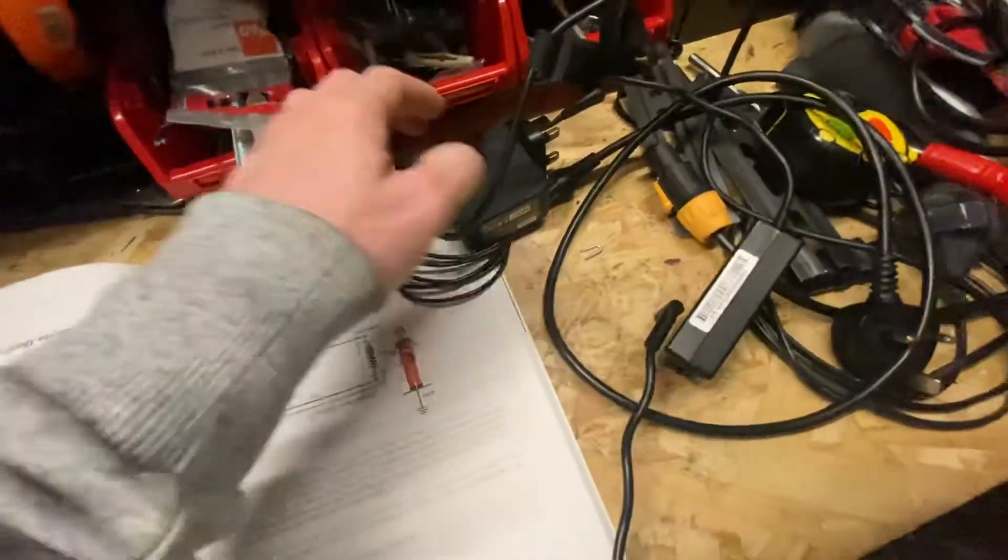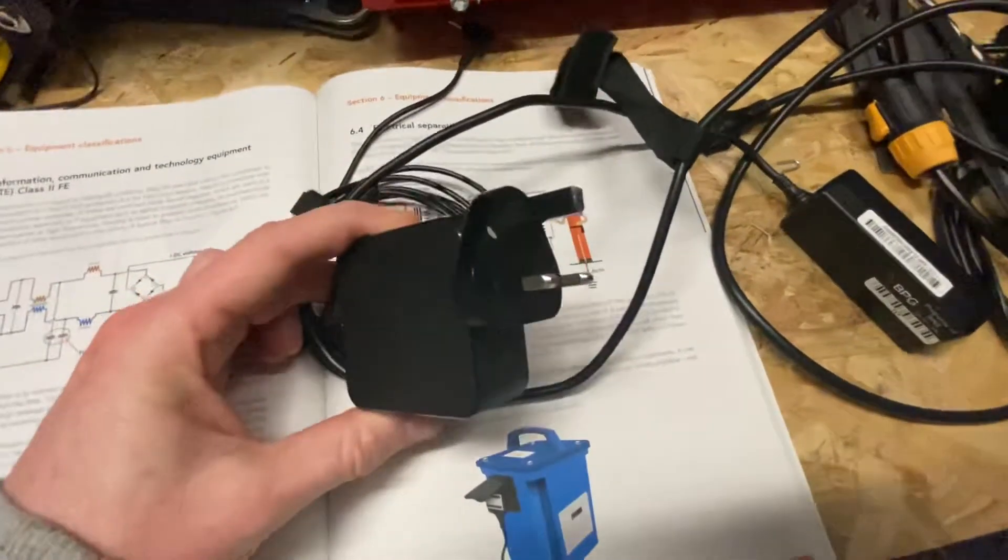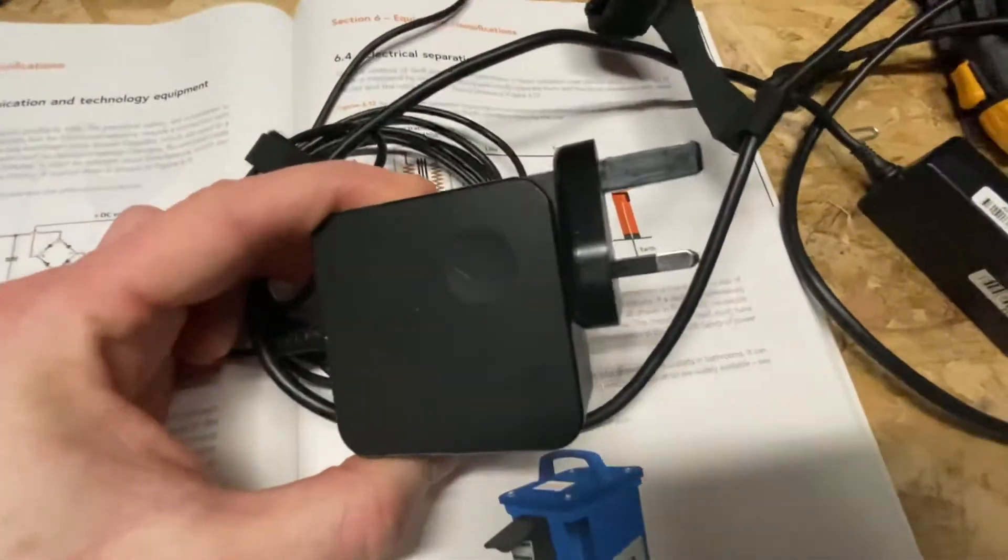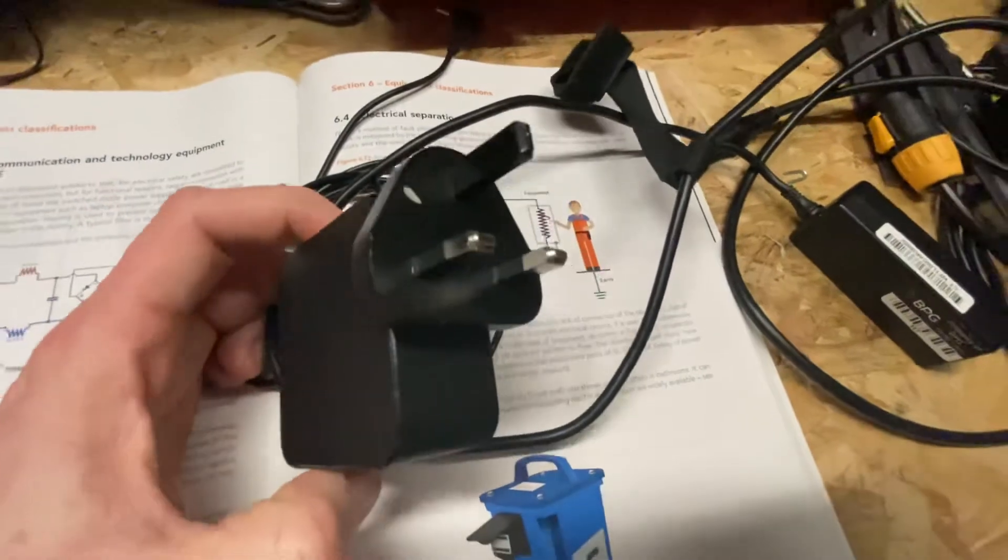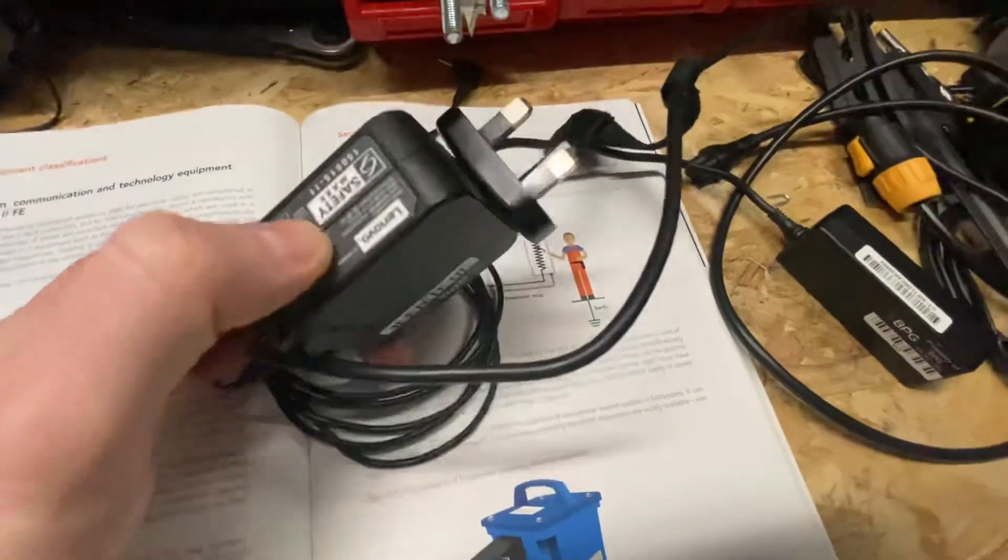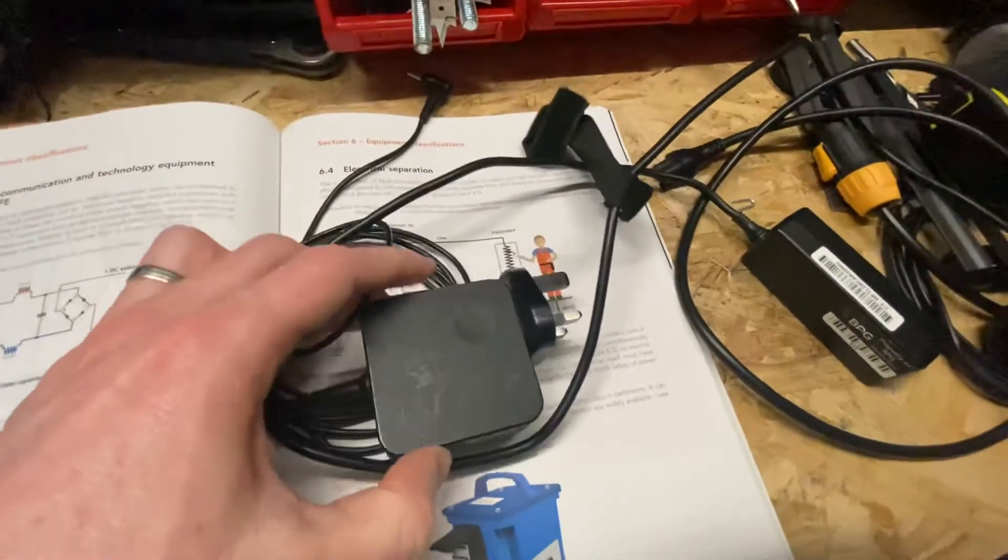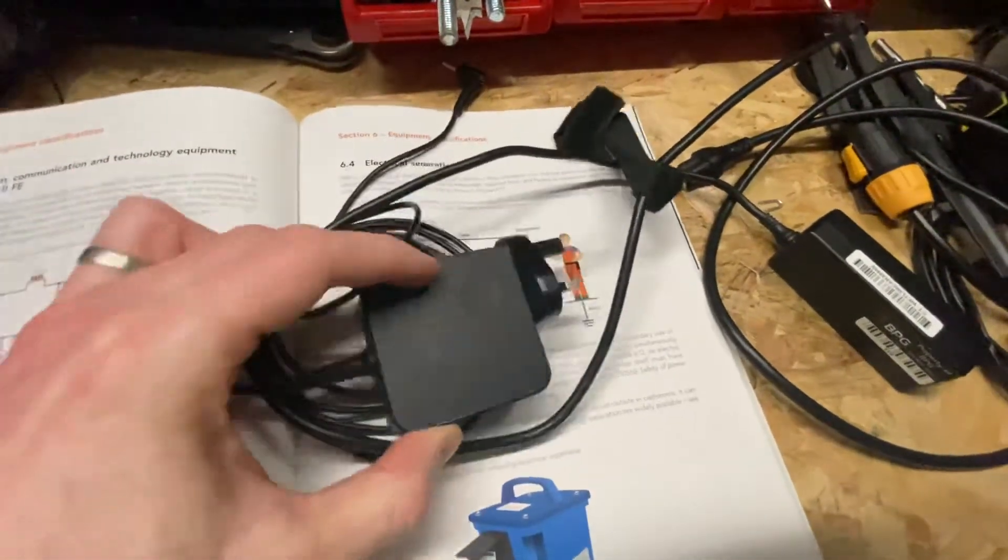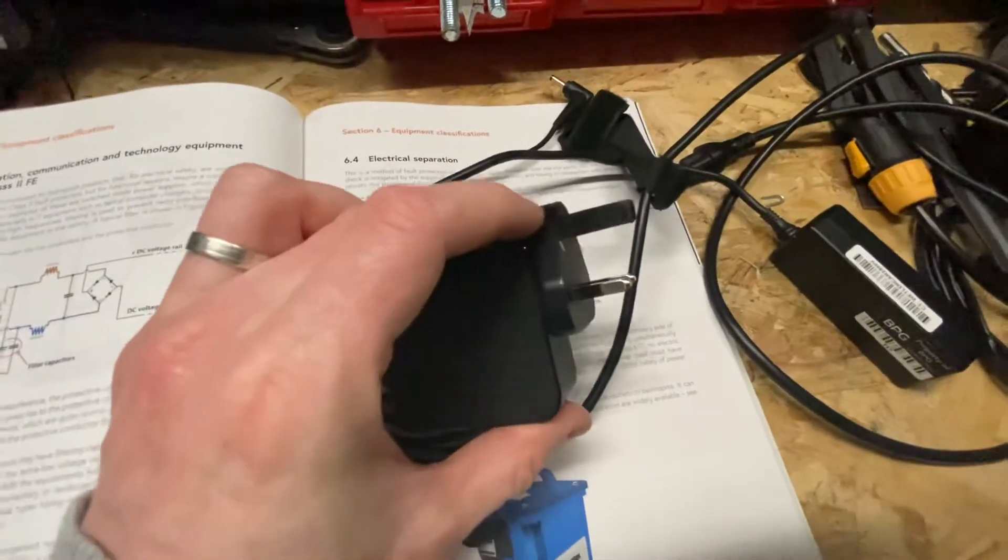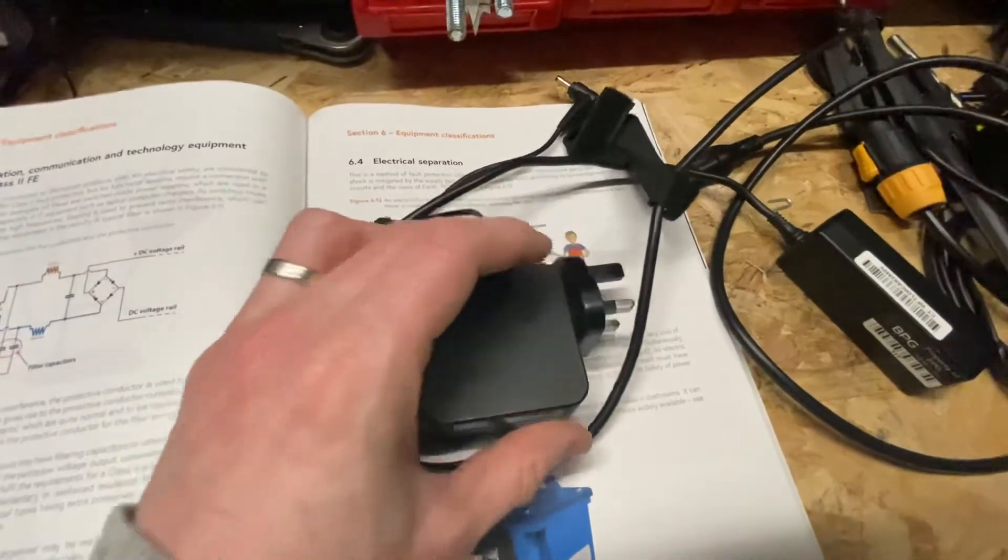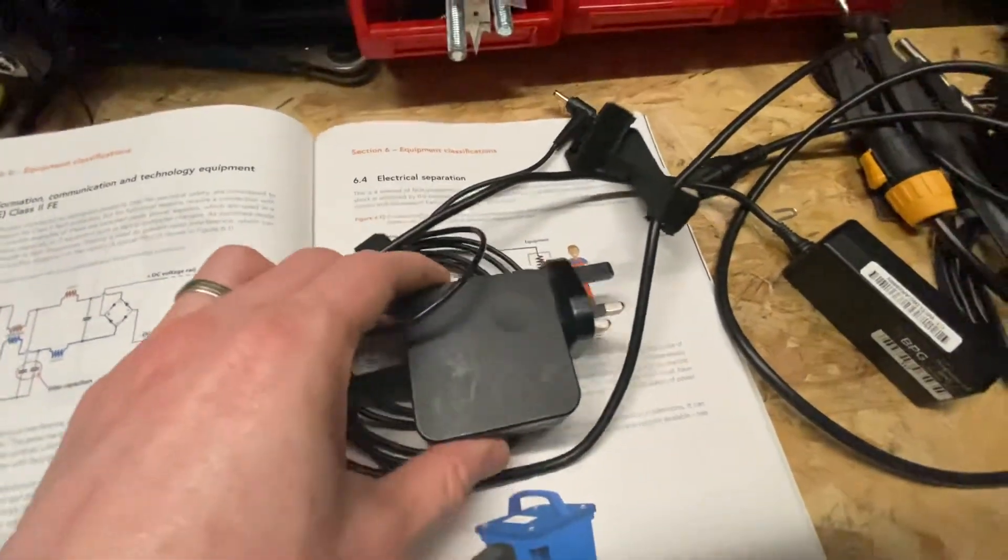And then with these here, as you can see, this particular laptop charger, it's got plastic pins there. You treat it as a class 2. Again, no exposed metal parts. It doesn't have that functional earth, so this is a slightly different design.